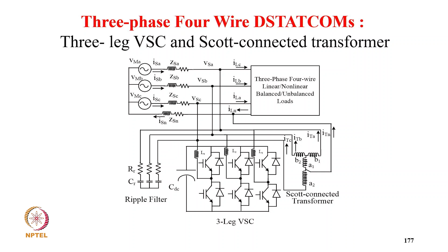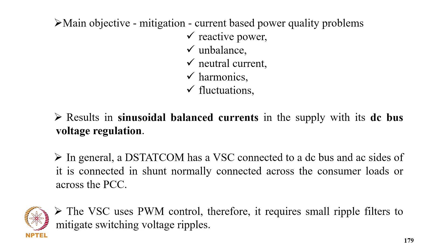So coming to the principle of operation of D-STATCOM. The main objective is the mitigation of current-based power quality problems like reactive power, unbalanced currents, neutral current, harmonic currents, and typically the fluctuation. So it results in sinusoidal balanced current in the supply with DC bus voltage regulation. In general, a D-STATCOM has the voltage source converter connected to a DC bus, and the AC side of it is connected in shunt, normally across the consumer load or across the point of common coupling. The voltage source converter uses pulse width modulation control, therefore it requires a small ripple filter to mitigate switching voltage ripple.